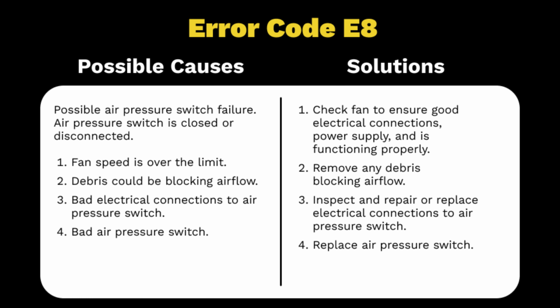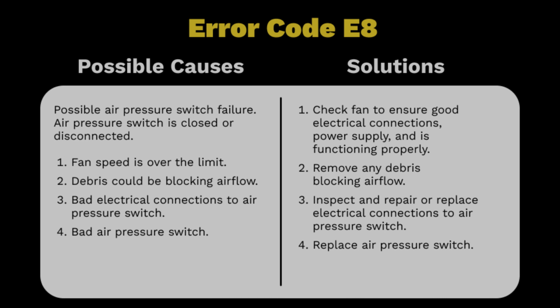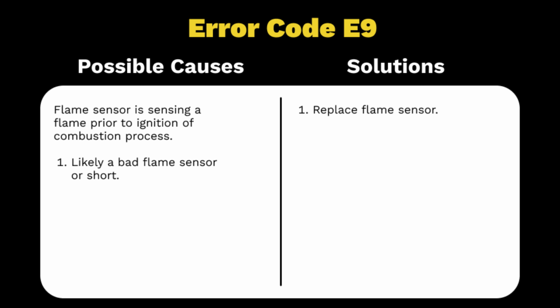If an error code E8 presents, it's a possible air pressure switch failure or debris is causing airflow restriction. Ensure the fan is functioning correctly and the connections are secure. If an error code E9 presents, this indicates that the flame sensor is detecting a flame before the combustion process starts. If the sensor is faulty, replace it.